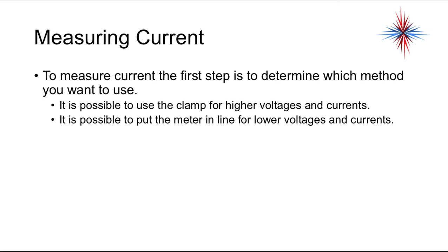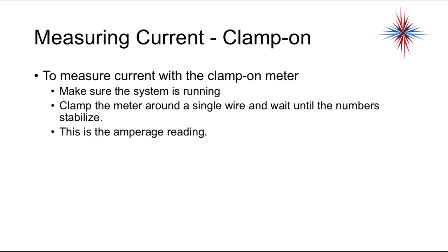To measure current, the first step is to determine which method you want to use. It is possible to use the clamp for higher voltages and currents. It is possible to put the meter in line for lower voltages and currents. Be very careful on the second one that you do not overwhelm the meter. Always try with the clamp first.